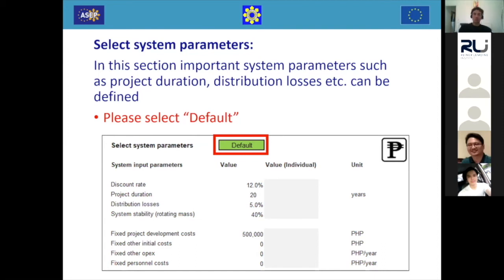And then we have the distribution losses, and we have the system stability, also called rotating mass, or also called spinning reserve. That's what Philip explained earlier. And we apply this stability factor as a percentage of the demand. So it means that 40% of the total demand has to be covered by a rotating mass. And for example, a rotating generator is the diesel generator. And this means that this generator can provide system stability.